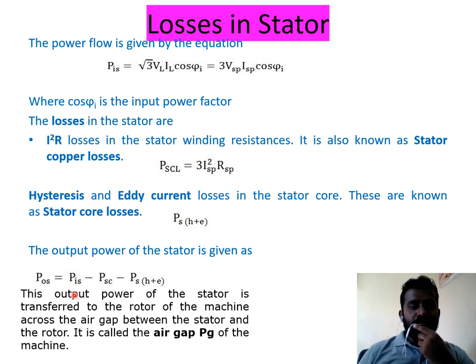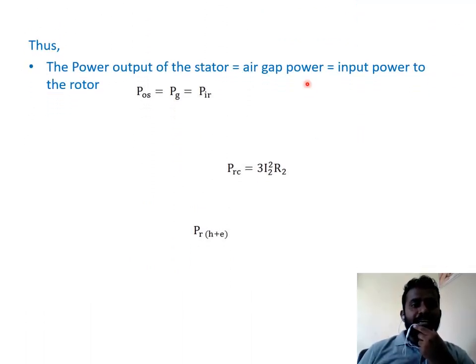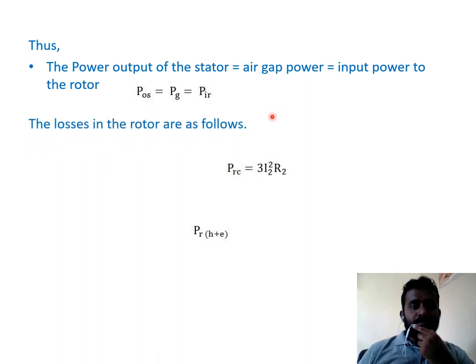This output power of the stator is transferred to the rotor of the machine across the air gap between the stator and rotor. It is called the air gap power PG of the machine. Thus, the power output of the stator equals the air gap power, which equals the input to the rotor. Pos equals Pis minus stator copper loss minus hysteresis and eddy current losses, as we have seen.